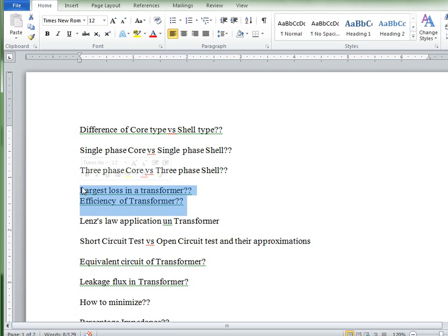Whenever you are designing a transformer and that transformer has to run for 24 hours a day, 365 days a year, unless there is load shedding or whatever, if you are designing a transformer for staying online for all its life, you always keep the core losses minimum. Right now it is daytime, there is nobody in the homes, but the distribution transformer near your homes has core loss all the time, it stays 24 hours, therefore it is kept low. Copper losses are kept on the higher side.